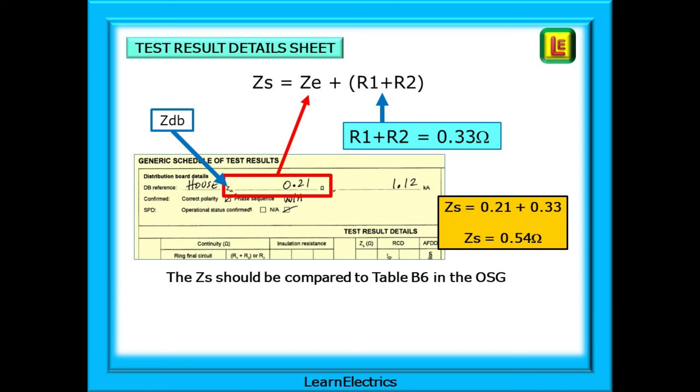For this example, take the 0.21 ohms for ZDB, and add it to the 0.33 ohms for R1 plus R2 from the test results page. 0.21 plus 0.33 is 0.54 ohms. And that is the ZS for this circuit.